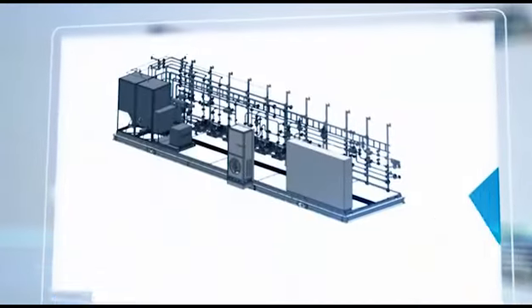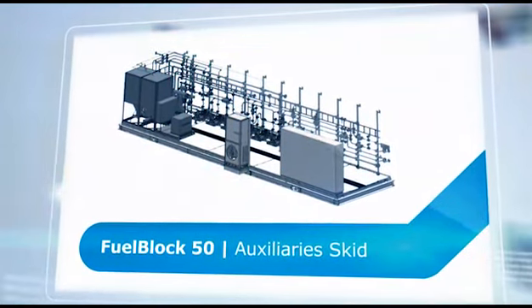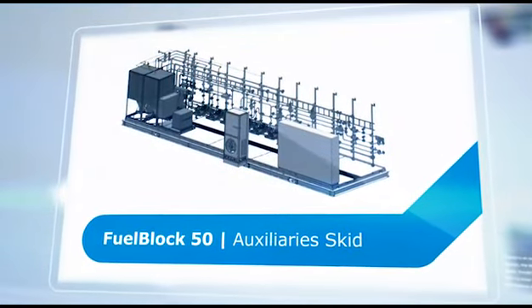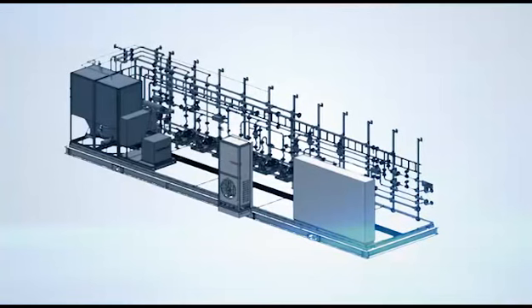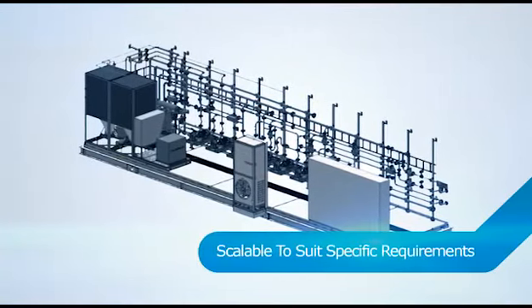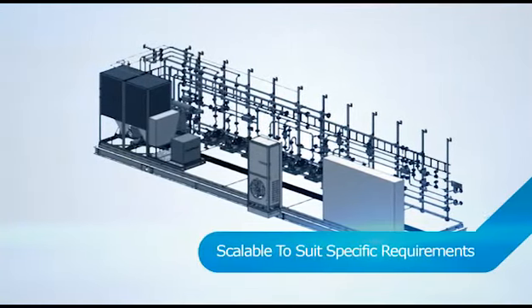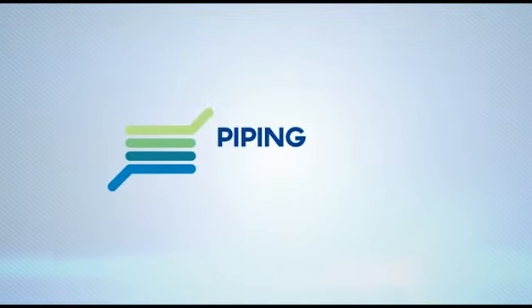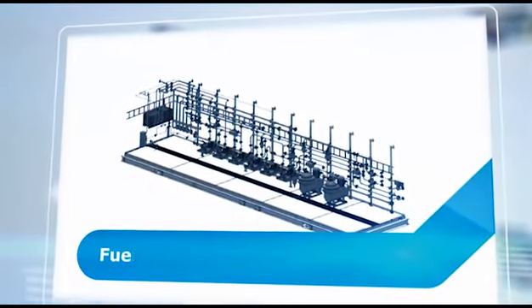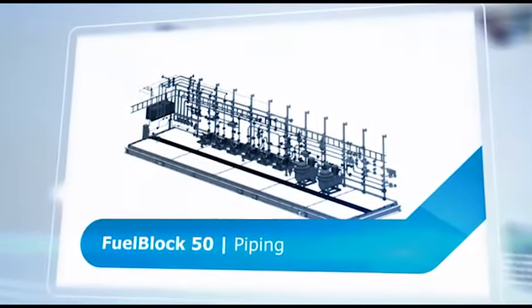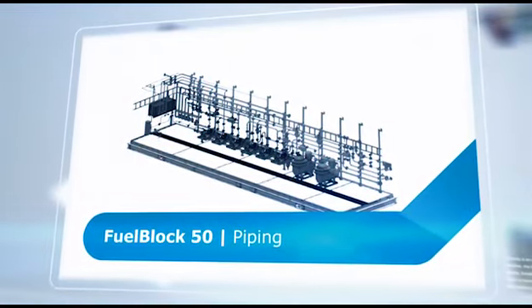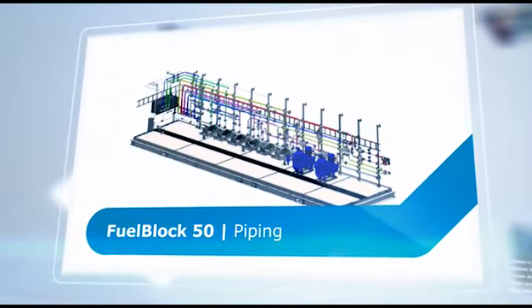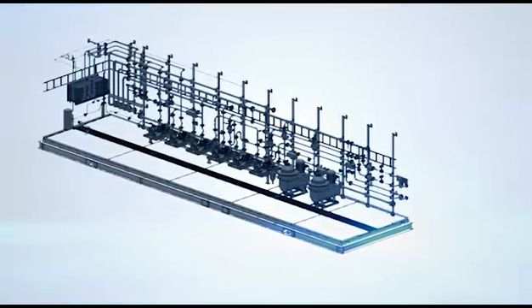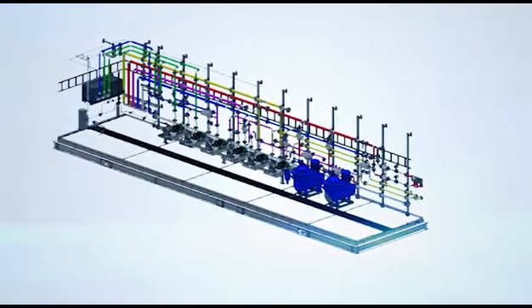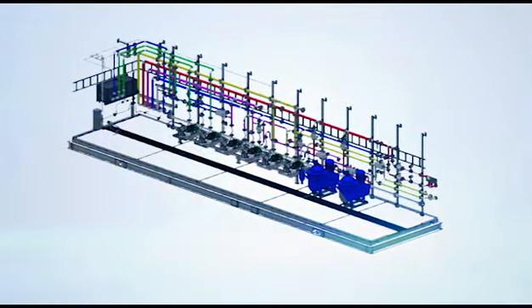The auxiliary skid is located along the same wall of the fuel block as the air conditioner, fire panel and MCC. It is modular in design and is scalable to suit the specific requirements of each site. All pipe headers, external piping connections and cable entries are located along the opposite wall to the MCC and auxiliary skid. Fuel tank connections are on the left, turbine connections on the right, with tanker unloading connections at the far left side.